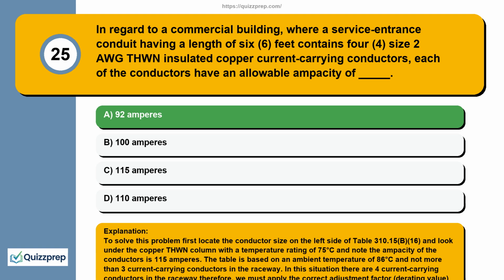To solve this problem, first locate the conductor size on the left side of Table 310.15(B)(16), and look under the copper THWN column with a temperature rating of 75 degrees Celsius and note the ampacity of the conductors is 115 amperes. The table is based on an ambient temperature of 86 degrees Fahrenheit and not more than 3 current-carrying conductors in the raceway. In this situation there are 4 current-carrying conductors in the raceway, therefore, we must apply the correct adjustment factor, derating value, as shown in Table 310.15(B)(3)(a), as follows: 2 AWG THWN ampacity equals 115 amperes before derating, 115 amperes x 80%, adjustment factor, equals 92 amperes.